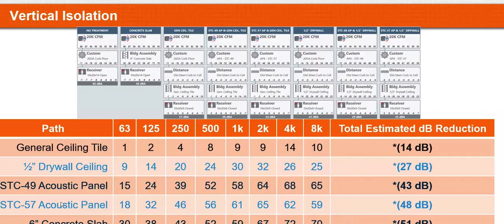So the combination of the treatment at the bottom or the isolation building element you have on the roof plus your ceiling type is going to get you the resulting sound level. You could get around 57 to 60 decibels by just using the typical 20 gauge with 2-inch liner floor at the curb, in a learning space that's not acceptable, or you could go all the way to an STC 57 panel with general ceiling tile also in the space, which will get you to 34 dBA, which is acceptable in a classroom because the max is 35 dBA. So just an example of where STC can come in handy for noise isolation.